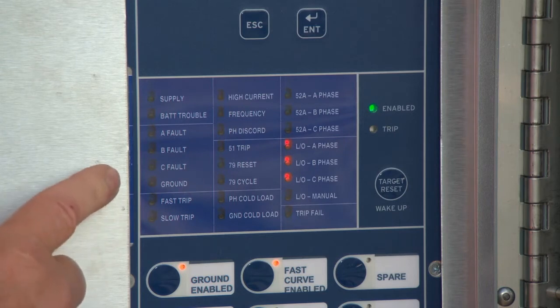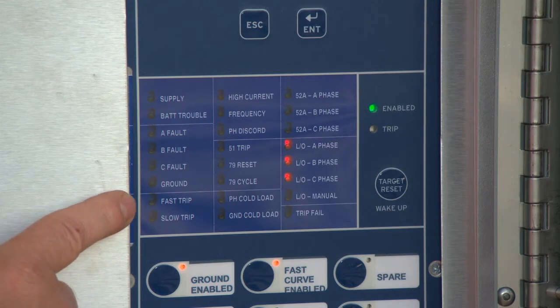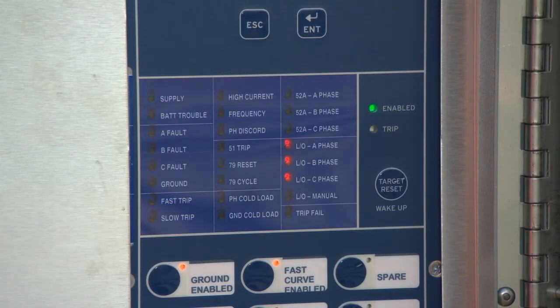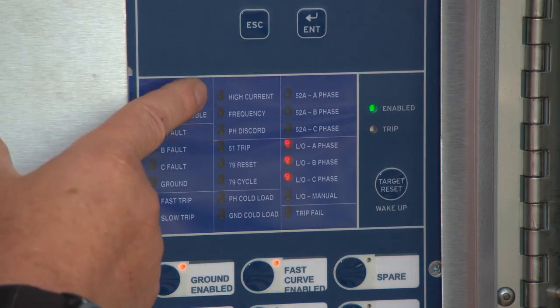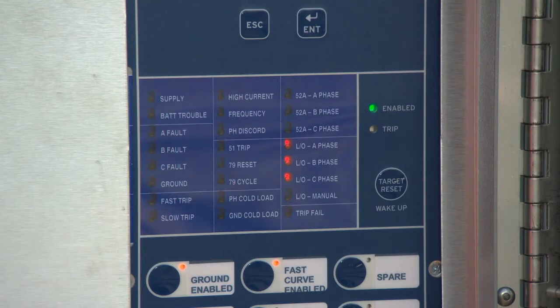Below this are the fast and slow trip LED indicators. Only the active timing curve LED will illuminate while the recloser is functioning under a trip condition. In the middle, we have an LED for a high current fault condition. This is currently not programmed into the controls. Were it programmed and it tripped on a high current, this LED would turn red.